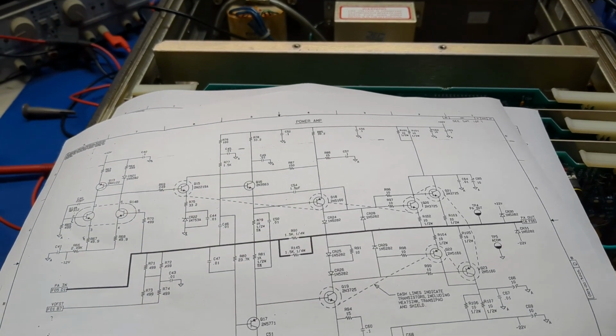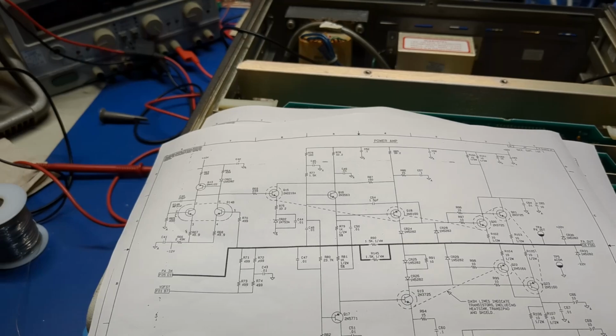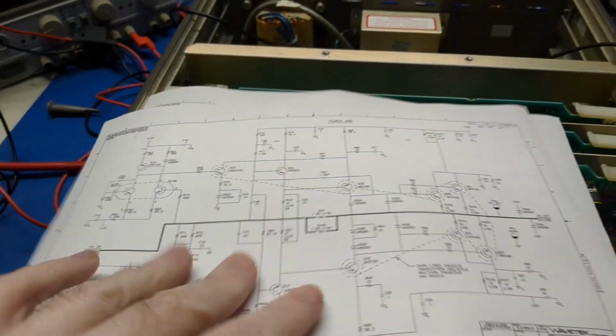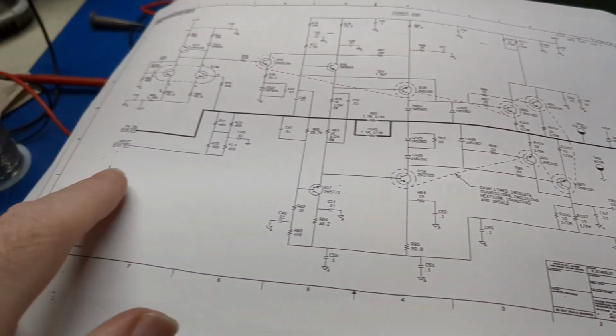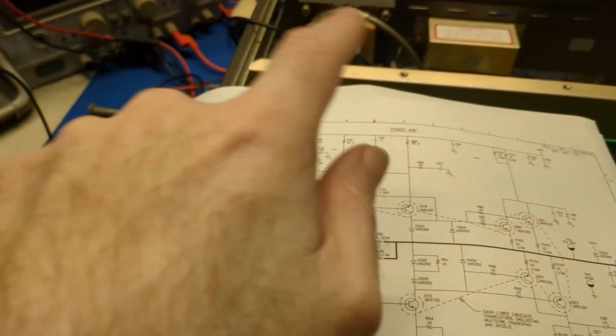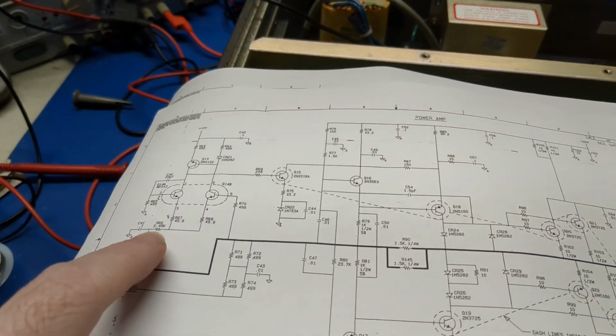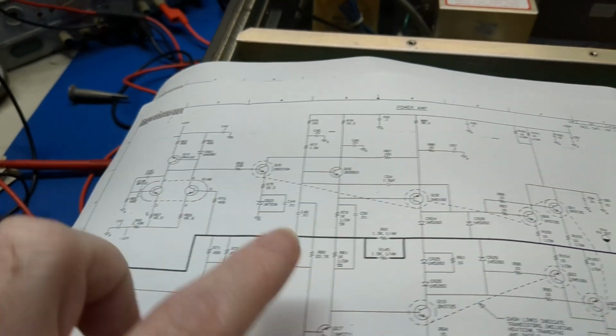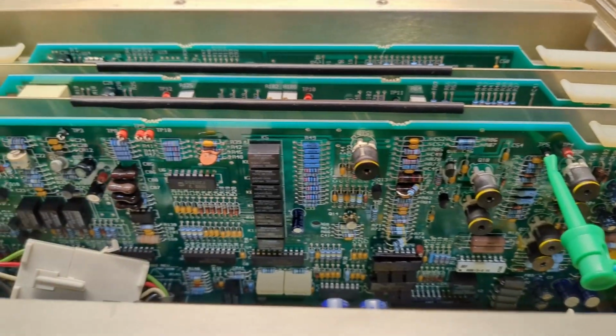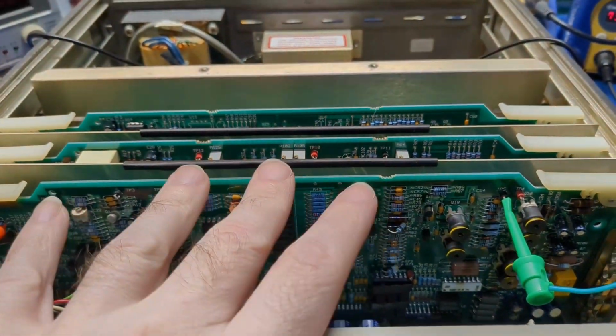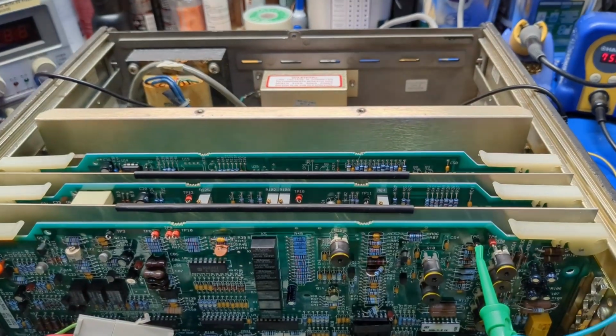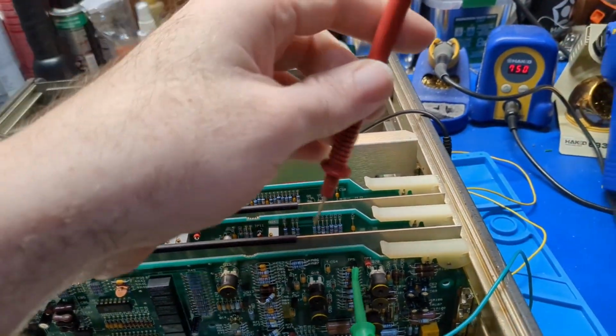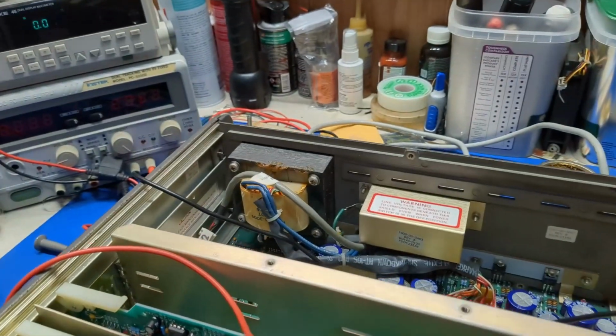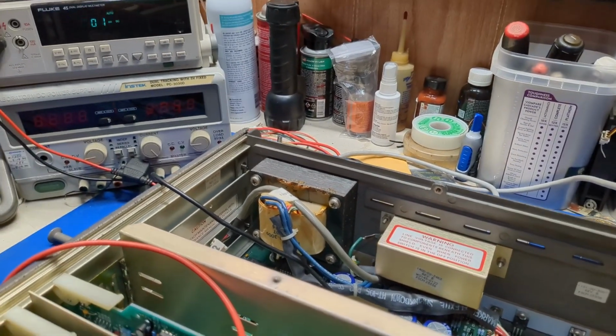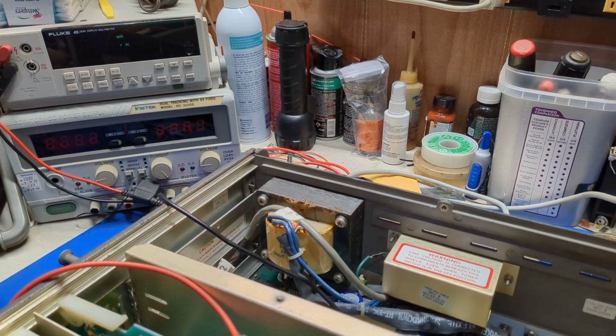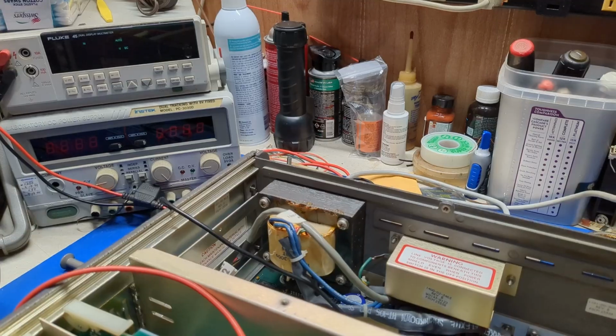So just to verify that I'm not doing anything stupid, I pulled out R73 and 74, which is down there at the bottom. R73 and R74 is the V offset input from the digital circuitry. And then the power amplifier input is on R70, which I also removed out of circuit. So the amplifier is effectively isolated away from the circuit. So that means if I put it on test point 4, which is our output on the amplifier, and I turn the power on, I still have like negative 13.2 volts there.